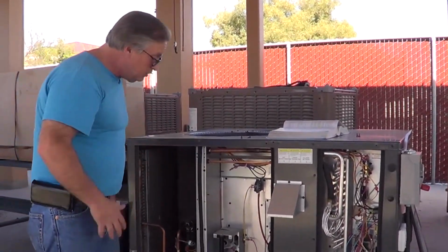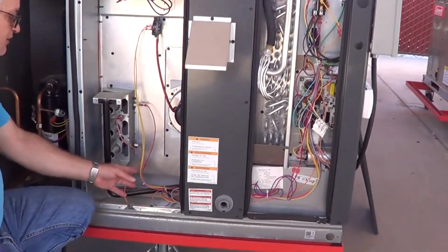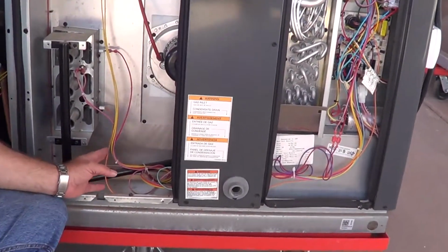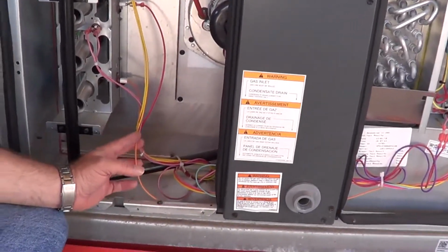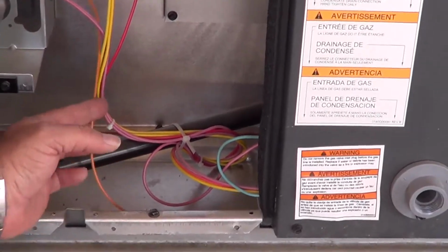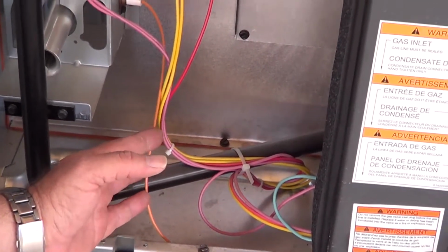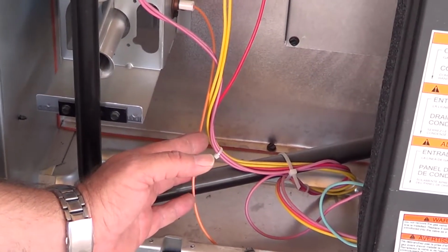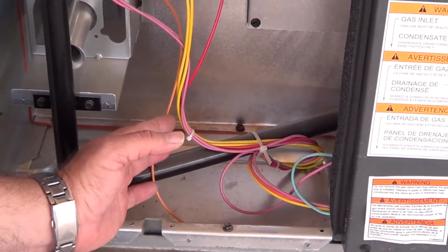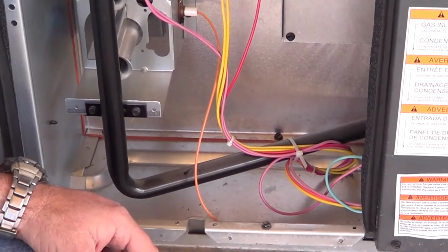Another thing I want to go across while we're talking about these components, we've identified the high voltage spark emitter here, and it ignites the burner as discussed. But that process also has to be proven for safety as well. In these modern furnaces, they are now proven by what's called flame rectification.